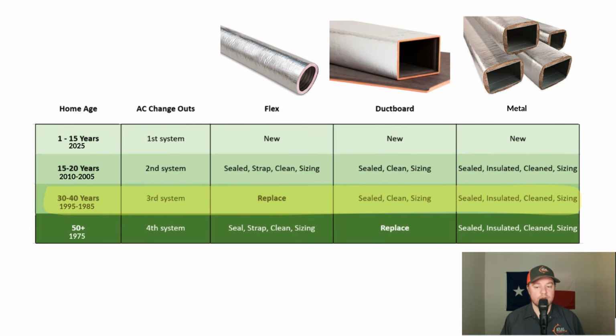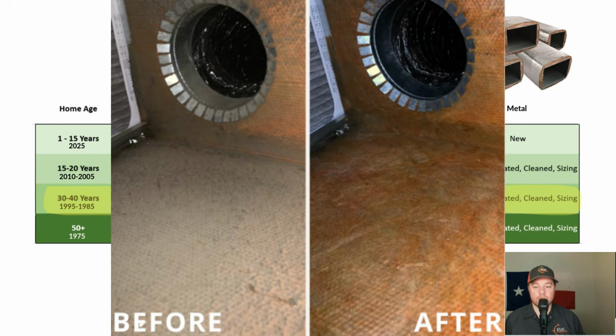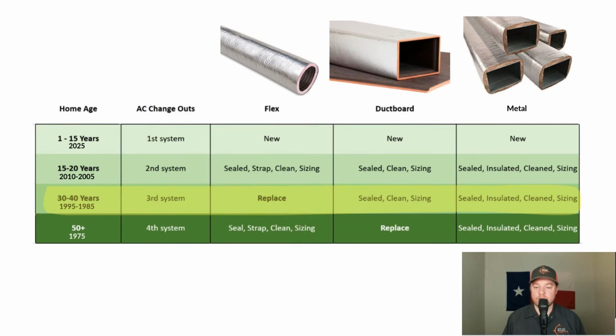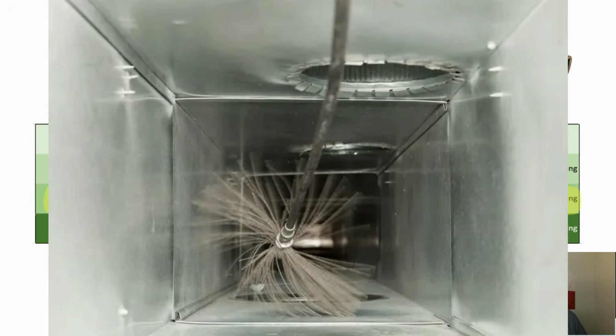If it ends up being dirty inside, you should be able to run a duct scrubber through it. And the downside of using a duct scrubber on ductboard is the inside is made out of fiberglass, so it could dust your home with fiberglass if you decide to clean it with a duct scrubber. And when it comes to metal ductwork, you shouldn't have a problem reusing it. And the beautiful thing about metal ductwork, you can run a duct scrubber just fine without damaging anything.